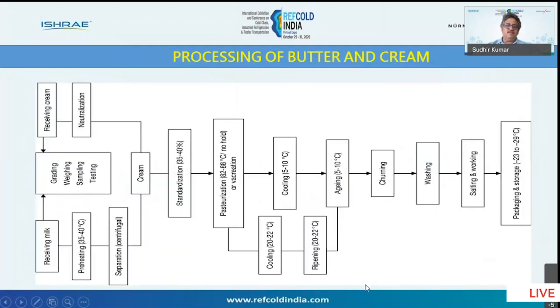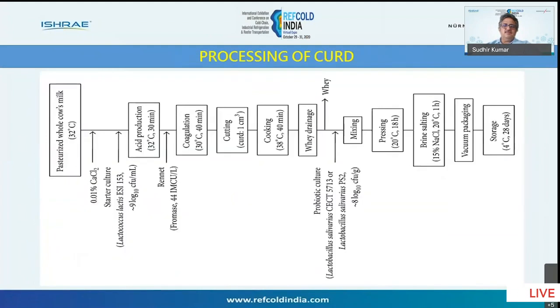Similarly, this is for butter and cream also. You will need cooling at aging tanks, cooling of the cream. Everywhere you need cooling, which is used by chilled water. And then afterwards, the storage is at minus 23 degrees, which is using direct refrigeration system. Similarly, for curd, this is the curd process.